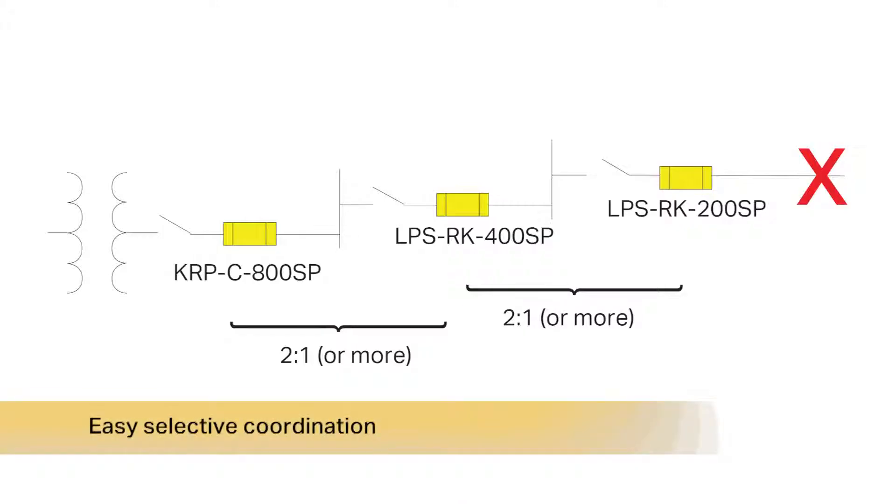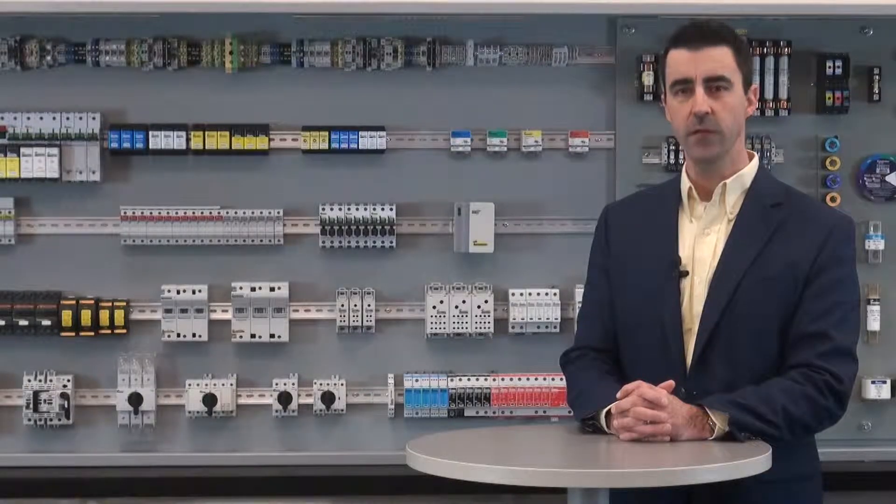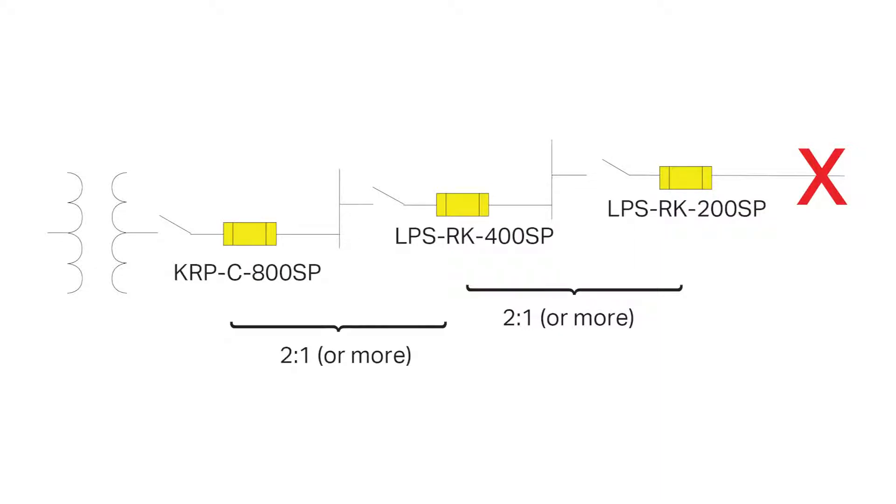Current limitation is a key part of selective coordination, and current limiting fuses save the engineer or designer time and money by reducing the need for a selective coordination study, as long as the minimum amp ratio is maintained between upstream and downstream fuses, such as a 2 to 1 amp rating ratio for Bussmann series low peak fuses. Selective coordination is achieved and unnecessary power loss to upstream circuits is prevented for any fault current up to the interrupting rating of the fuse.